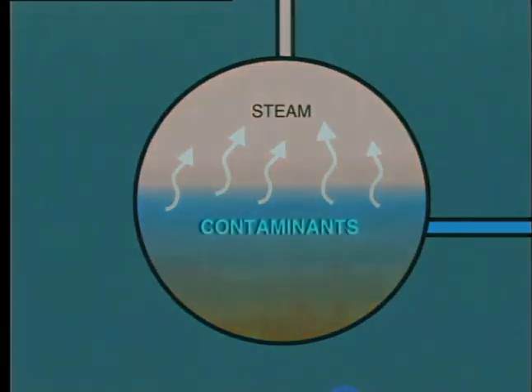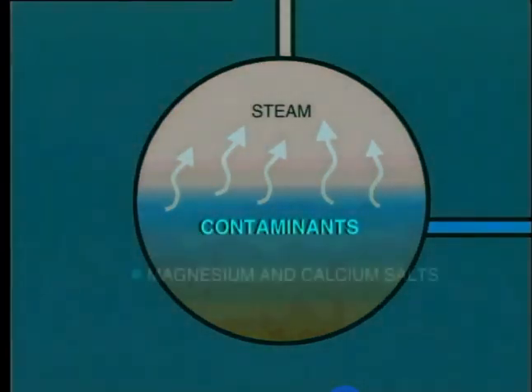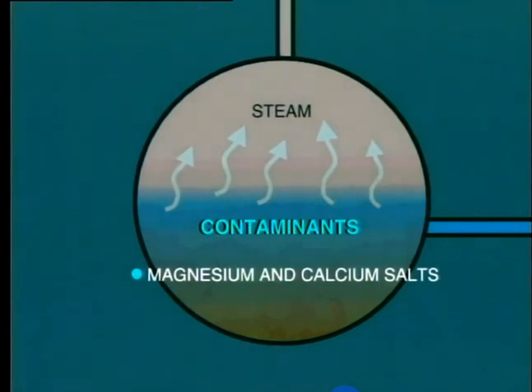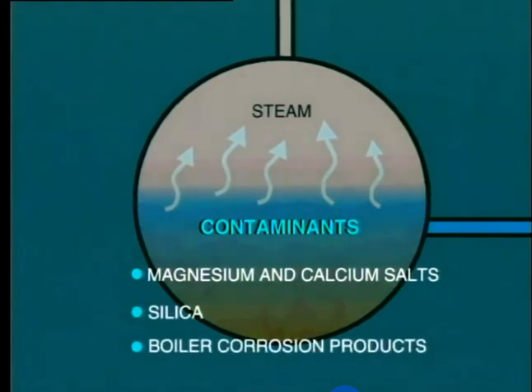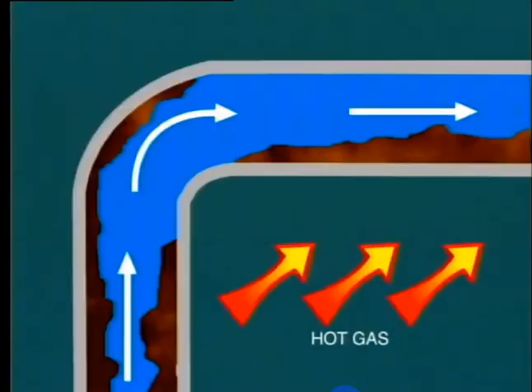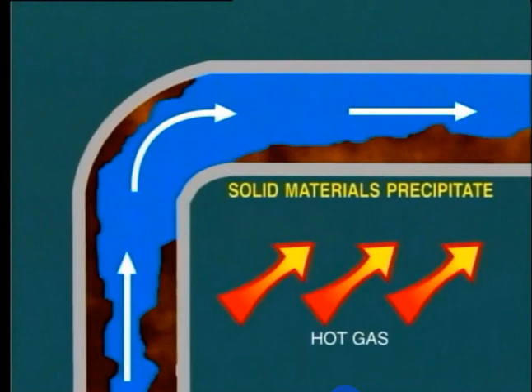Generally speaking, the contaminants consist of magnesium and calcium salts, which are dissolved in the water and contribute to hardness, silica, the products of corrosion of the boiler itself and the feed water system — mainly iron and copper. At high temperatures such as encountered in boiler water, and above a certain concentration, these solid materials precipitate out of solution and deposit on the inside of the tube wall.